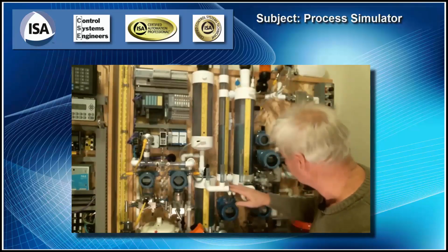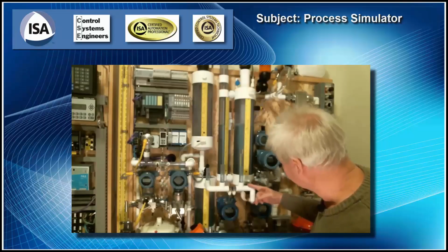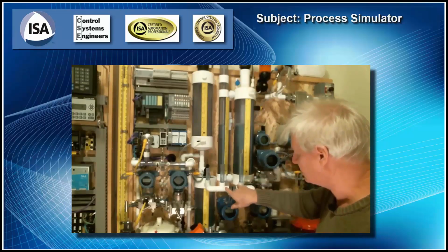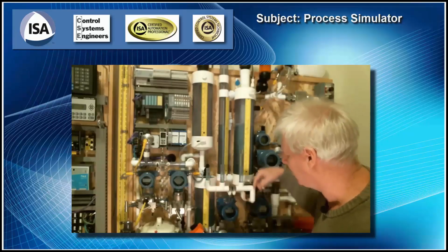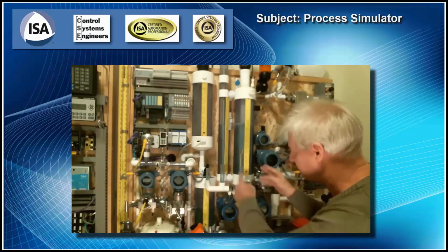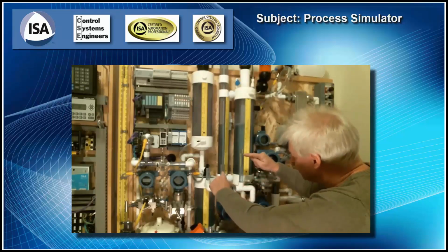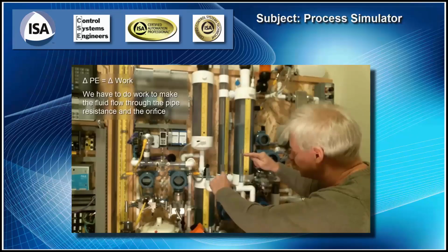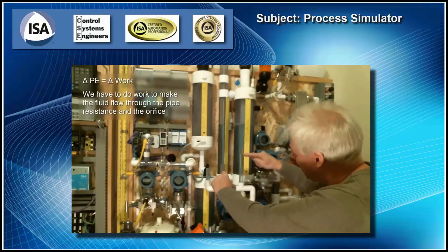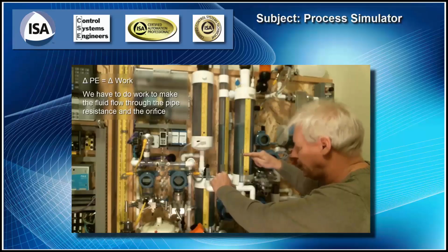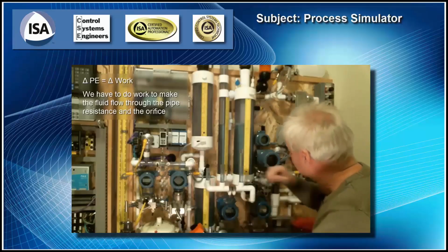Mass times acceleration equals force. And we get a voltage drop or a pressure drop across each one of these sections of fittings and pipe because of resistors. Just like you measure a voltage drop across a resistor, we measure a potential. The potential in head is the same as the potential in voltage. It can be thought of as the same thing, and we can see a difference of pressure across here, or a difference of head and potential energy. So we have a difference of potential energy.